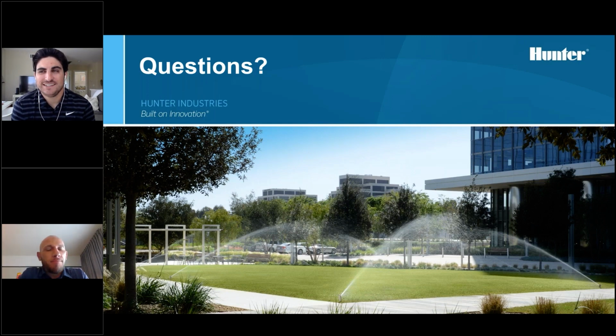But no, I think one of the largest benefits that I felt personally in the field, and the light bulb goes off, it's so simplistic but so great, is the green LED indicator light on the decoder. I mean, you're using existing equipment. If you're a quality contractor, you've got a good voltmeter in hand, right? So you're running a zone, you don't see visually atmospheric irrigation in that area, you go to valve box location, open it up. If you don't have a green flashing light, but you have 24 volts, 60 hertz at that location, rip it out and replace. It's that simple. You know what I mean?